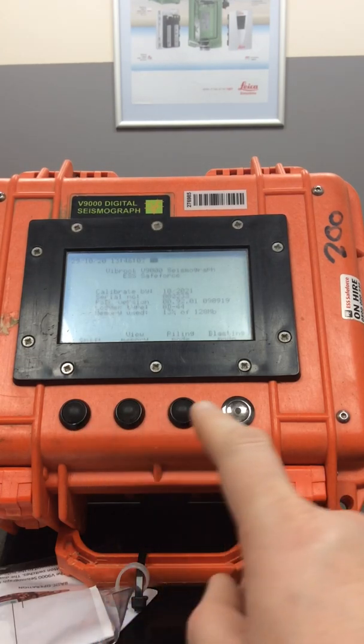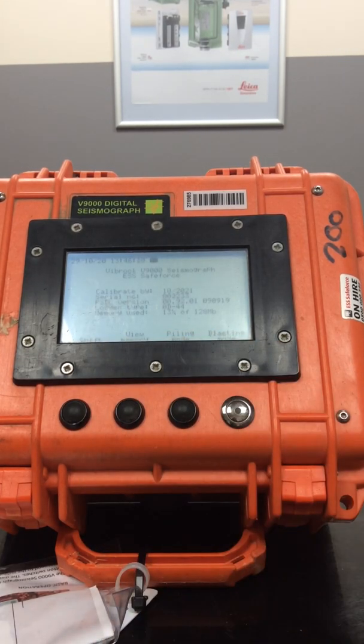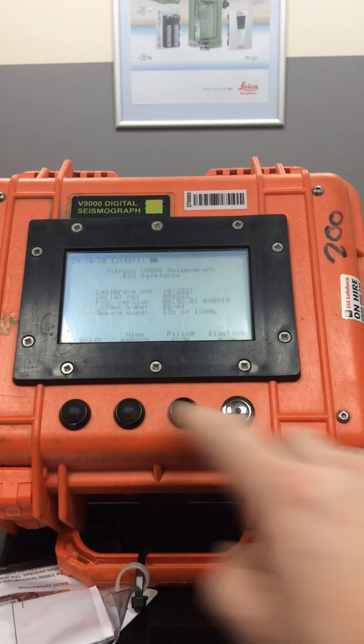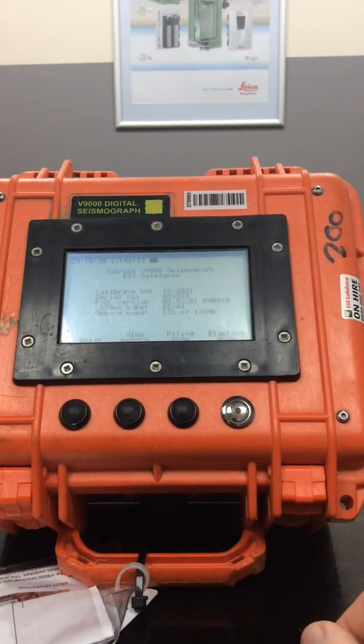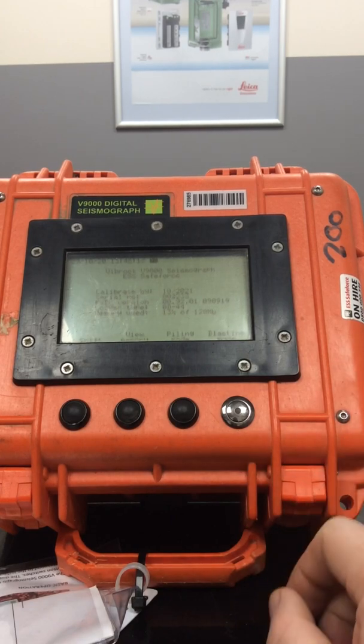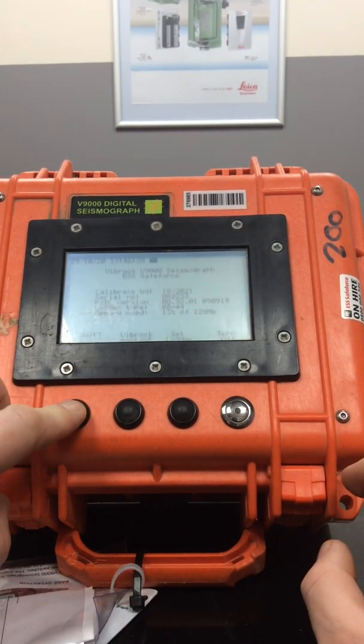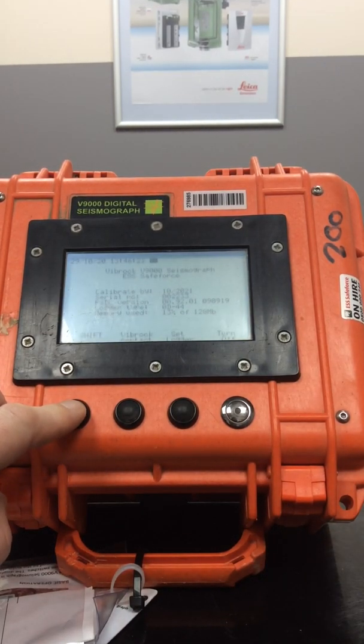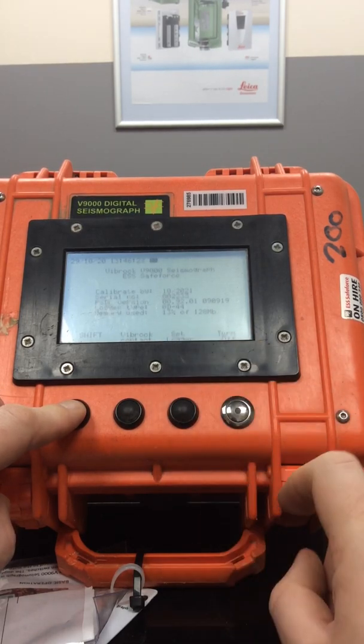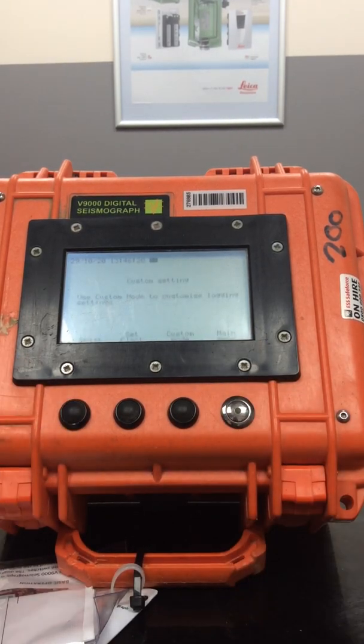All right, and you can see along the bottom of here, whatever corresponds with the buttons below is above. At the moment we've got shift, view memory, piling, or blasting mode. What we need to do is press and hold the shift button, and it changes the description for that button there. We want set logger, so press set logger. This takes us into our custom setting mode.